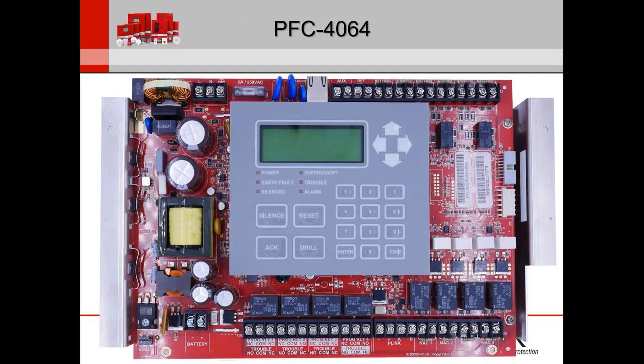Here's a look at our board. The first terminal is the PCOM network connection — this is how you upload and download to and from the control panel, utilize email capabilities, or send signals to the central station via IP. You have the AUX power circuit, rated at 1 amp, which can be used for door holder power, resettable power, or constant power. Then you have your six IDC or initiating device circuits — six Class B or three Class A.